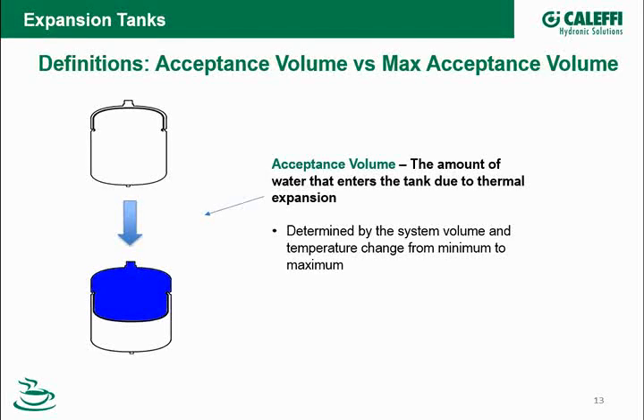Now, the other thing that we have to talk about from a definition standpoint is what's called acceptance volume. Acceptance volume really is a function of the system. Where I design a hydronic system, I have a certain volume, I have a certain temperature range. That's going to mean that the water expands to a certain point. So when I look at tank sizing, I have to make sure that the tank can take the acceptance volume.